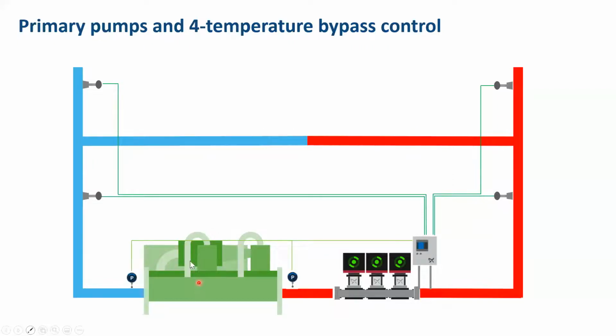Once that is satisfied, then we'll look at this 4 temperature bypass here. So this is our exploded bypass with 4 temperature sensors on the supply and on the return. Ultimately what we want to do is maintain 0 flow across this bypass, and that would give us our balanced system. So if we take a closer look, our balanced system is represented by a zero delta T across the bypass. So our chiller is operating, we're going out at 44 degrees. All of that flow is going out into the system. That chilled water is moving through air handlers, it's picking up heat, and it's returning at a nice 10-degree delta T in this case, and then flowing right back to the chiller. So the system is balanced, either full open or partially open. We've got a good balance across it.